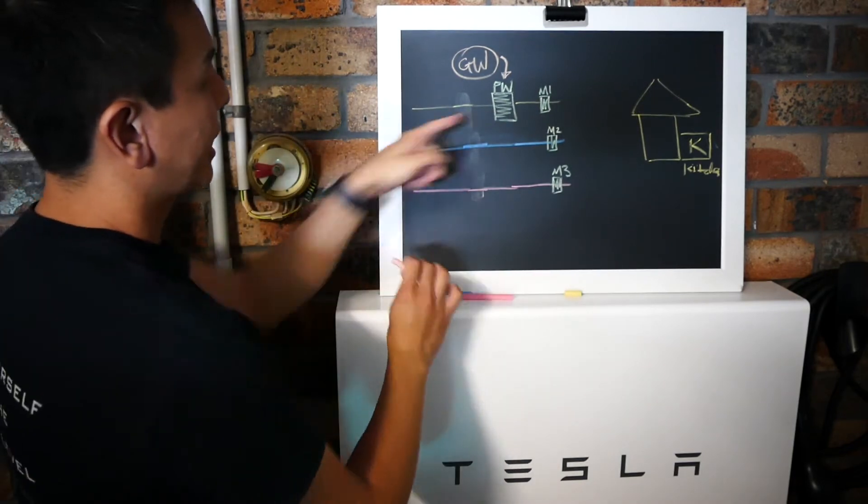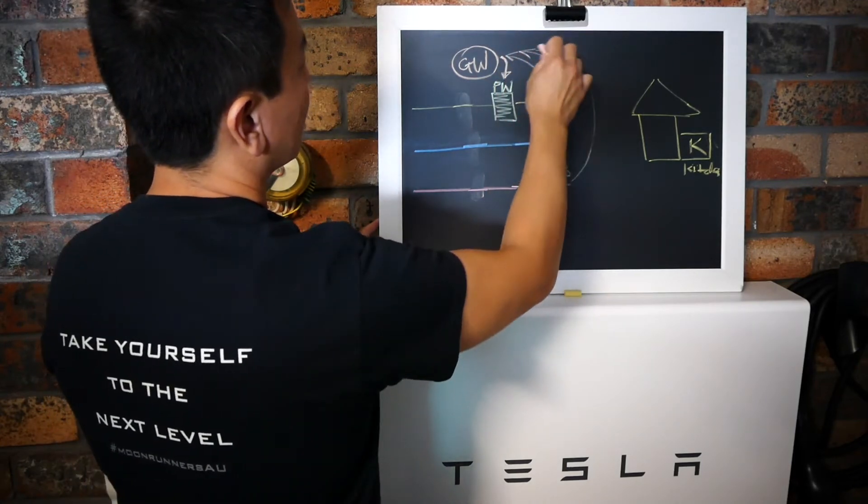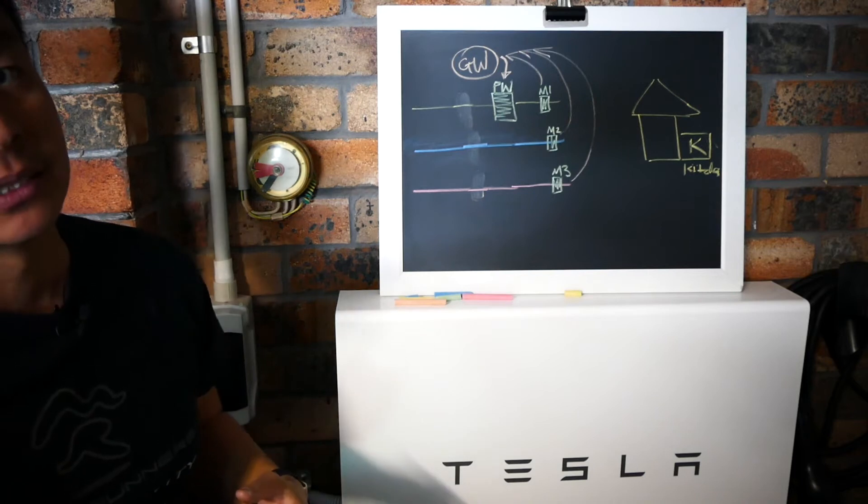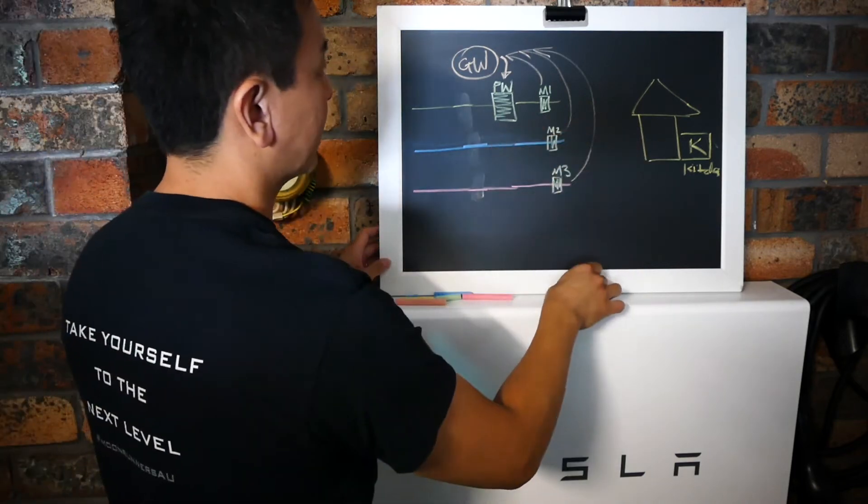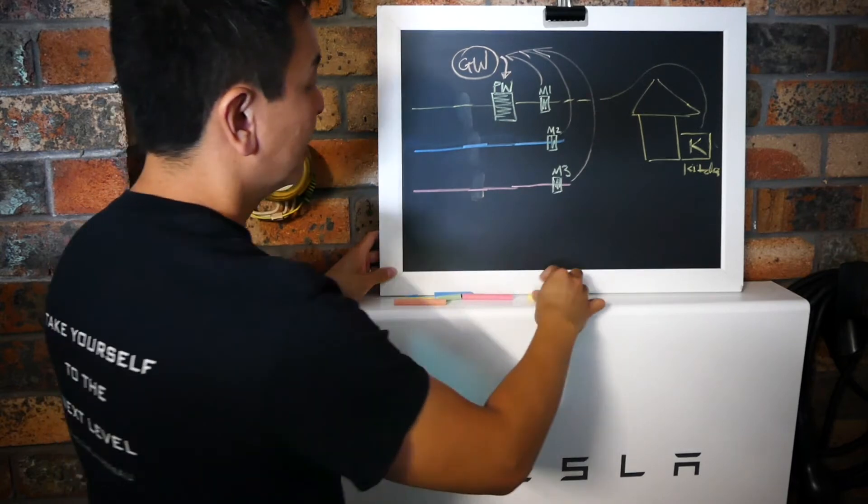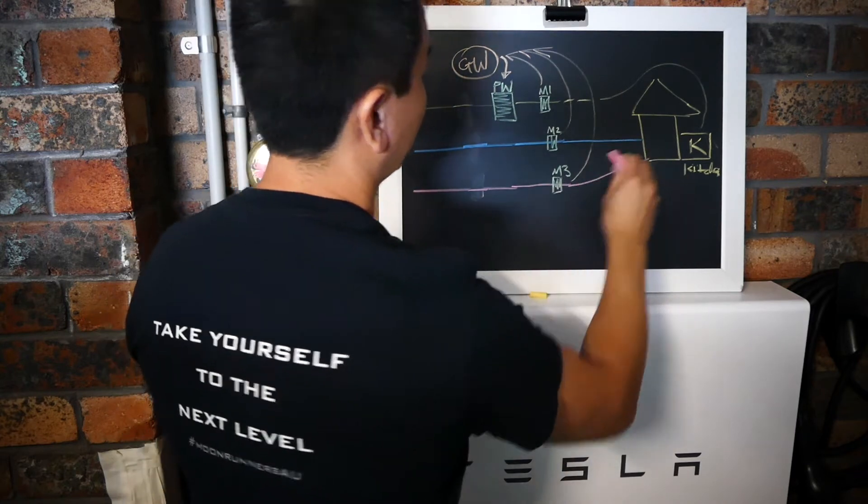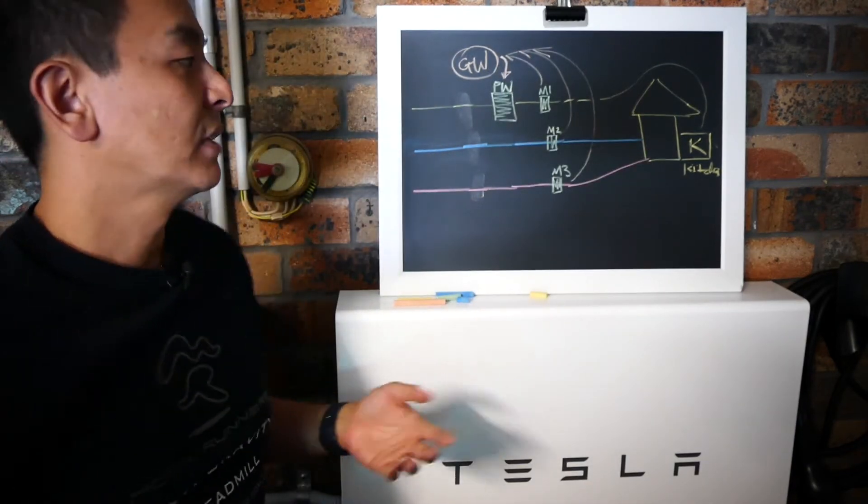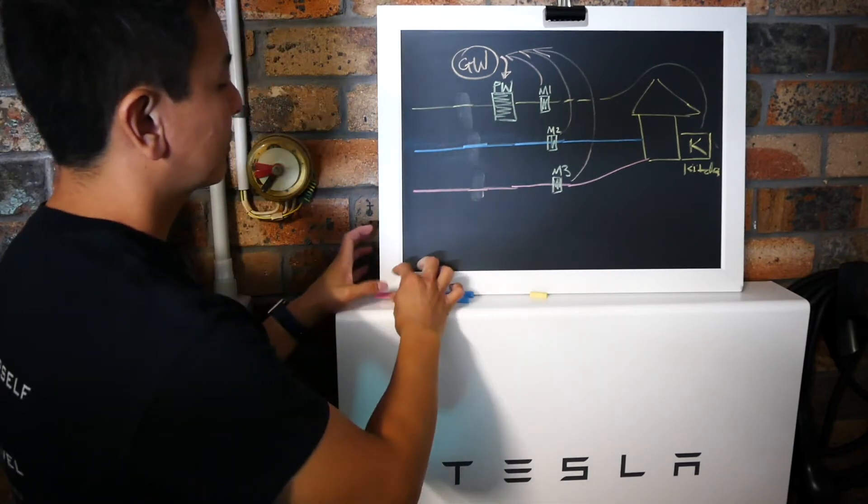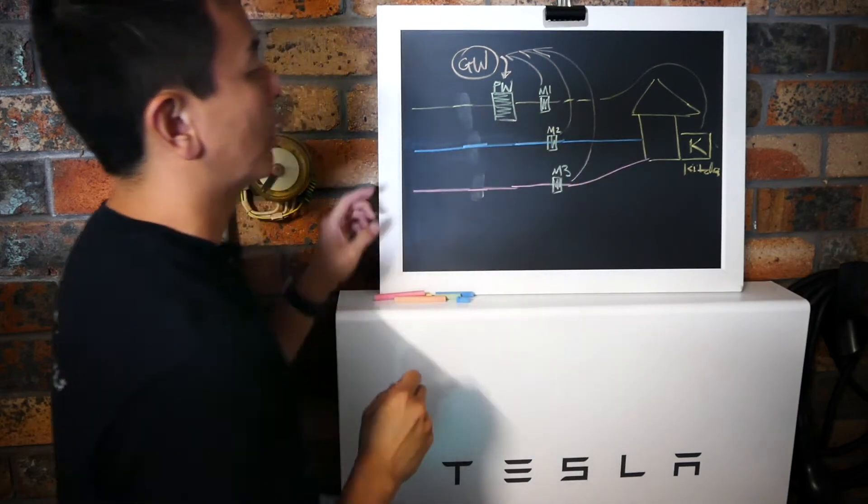So like I said before the Powerwall 2 only supplies across one phase because it's a single phase unit. The Gateway 2 has meters that tells it how much electricity is being used currently in the house. So the Powerwall normally best practice is hooked to your essential kitchen appliances. That's where most of the Powerwall supply. The rest of the house is supplied by the other two phases generally speaking. That's usually the best practice. Upstairs, air conditioning, the pool if you've got a pool pump, your computers, your fans, all those kind of things. In a normal situation, so the kitchen will be supplied by the Powerwall when it discharges.